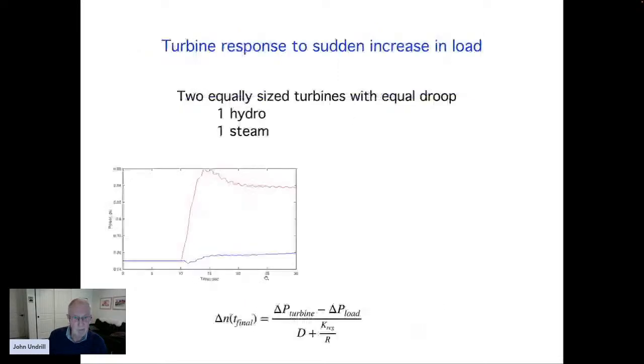Now let's go on. So let's consider this. I have a little power system running somewhere. It's not connected out to a very large grid; it's connected within itself. It could be a couple of gas turbines on a gas production platform in the North Sea. It could be a large paper mill somewhere in Scandinavia operating with a hydro generator and a steam generator. It could be a refinery somewhere in India that, because of an emergency in the transmission system, is operating with its own generation, separated from the local grid.